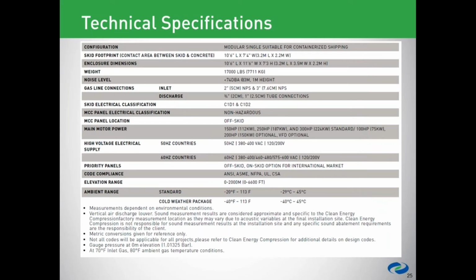On international packages where we offer an on-skid priority panel, you would actually have a number of outlets corresponding to the style of the priority panel that's used. So on a single line priority, one discharge line to the dispenser connection and one to the storage connection. On a 3-line, you would have 6 outlets, 3 to dispensers, 3 to storage. So in general, it's a single outlet line, but that depends on the priority panel option chosen.